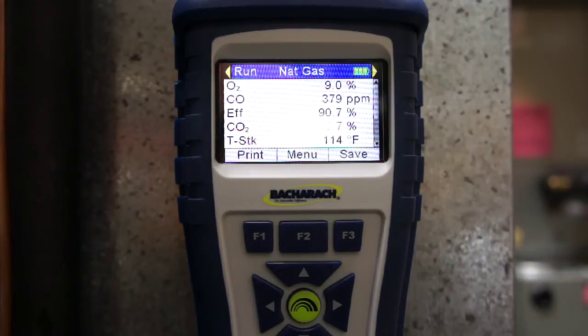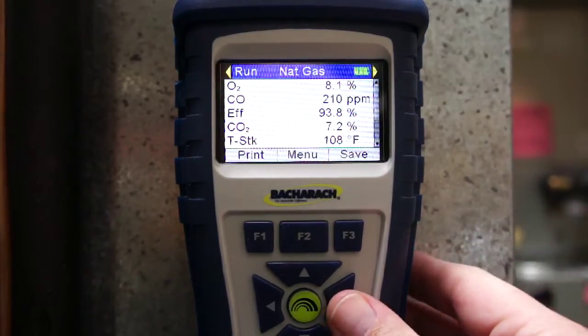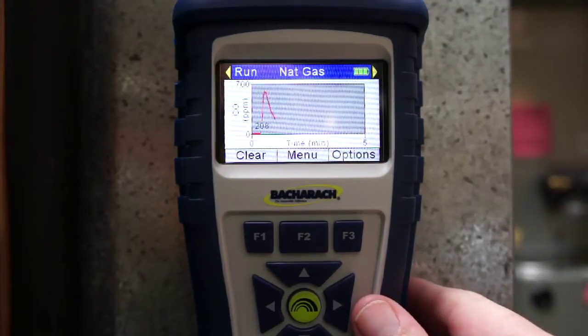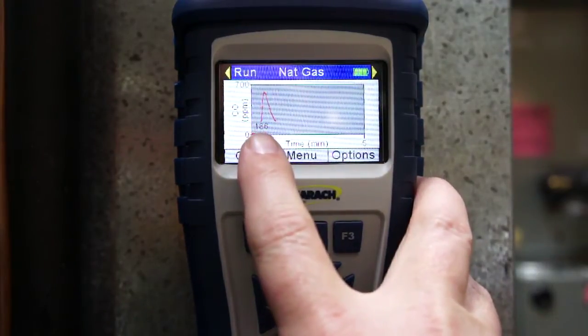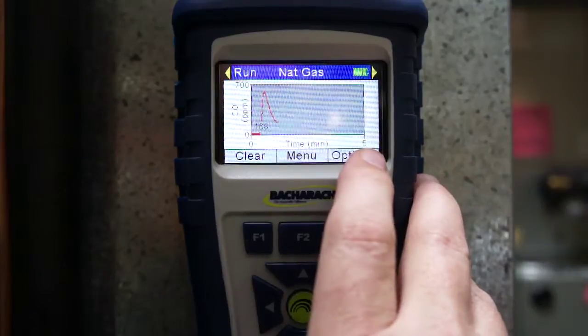But you may wonder, well, what was that? Because maybe you weren't paying attention as it went by. And here's where the analyzer really shines. They've done a lot of things with the menu structure. So now we're looking at all our regular combustion readings. But if I go ahead and hit the right side of the display, I can actually see a trend now of how that CO actually looked. And right now I have it set up from 0 to 5 minutes.